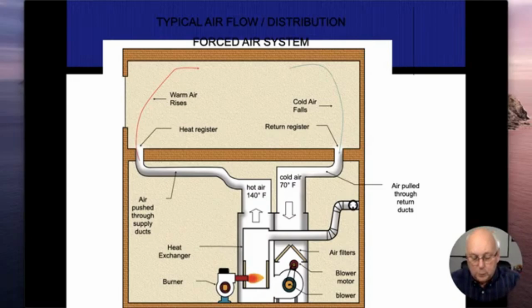Now, they're showing this where it almost looks like the vent or the vent connector is going through the return air. Yeah, there was a very short time frame where that happened, but we don't do that anymore. Pressure differentials are very important in the safety of how these heating units work. All right. So first thing we want to do is talk about the airflow.